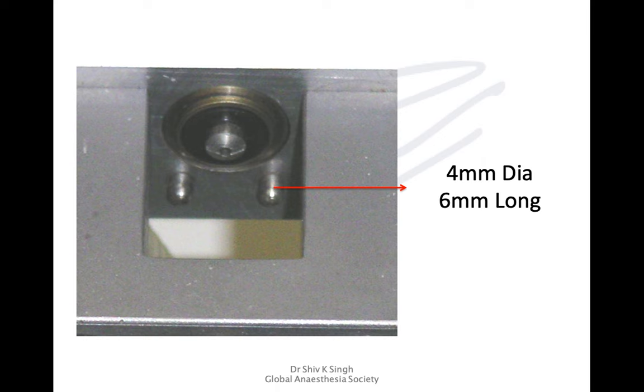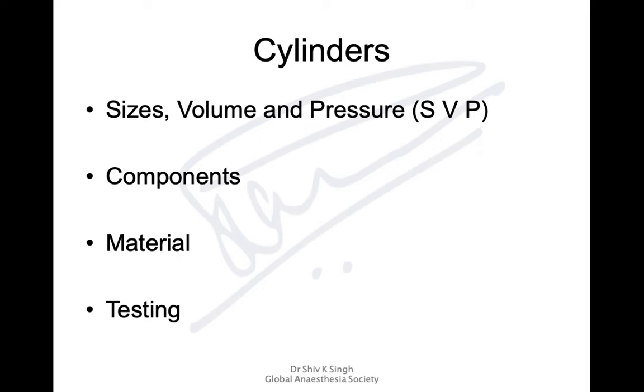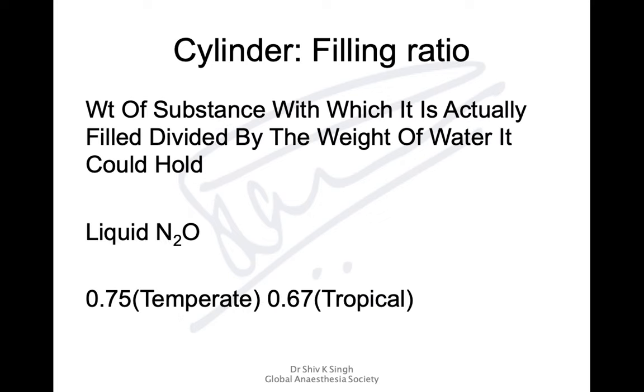Cylinders are important and you need to know their sizes, volumes, pressures, materials, and testing procedures — important for examination purposes. For liquid nitrous oxide you need to know the filling ratio: the weight of substance it is filled with relative to the weight of water it could hold. In temperate climates this is 0.75, while in tropical climates it is 0.67, because higher temperatures more easily convert liquid nitrous oxide to gaseous form.